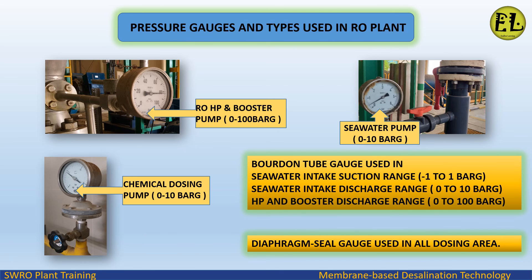Pressure gauges and types used in RO plant: Bourdon tube type gauges are used from seawater intake to the product system. Seawater intake suction range: -1 to 1 barg. Seawater intake discharge range: 0 to 10 barg. HP and booster discharge range: 0 to 100 barg. Diaphragm seal gauge types are used in all dosing areas.